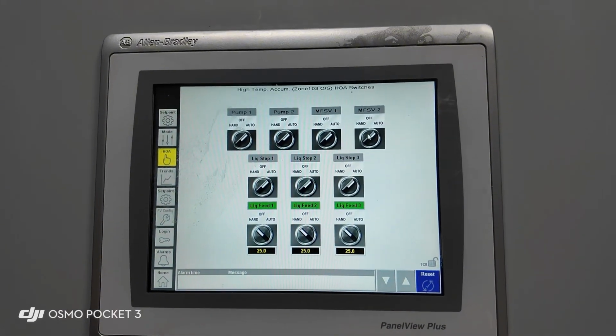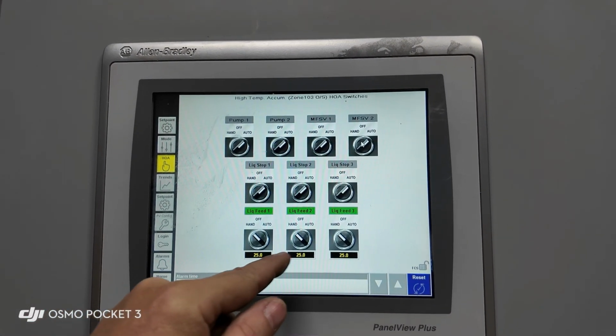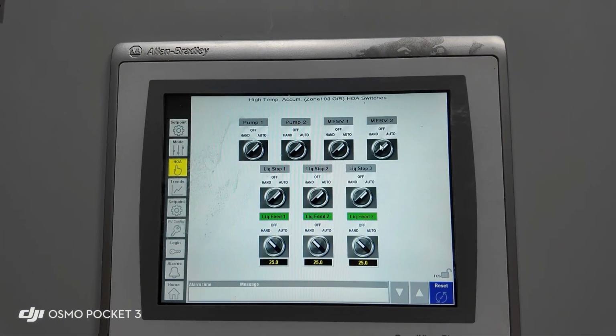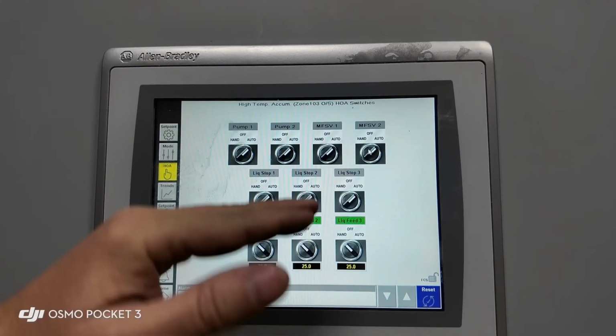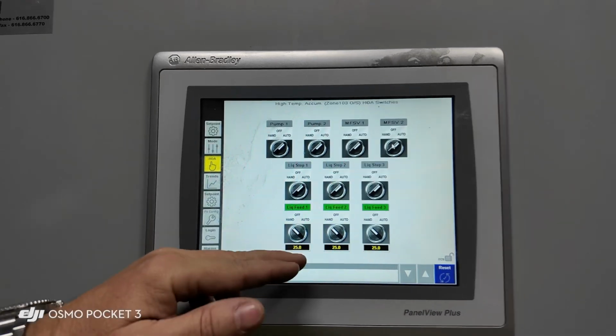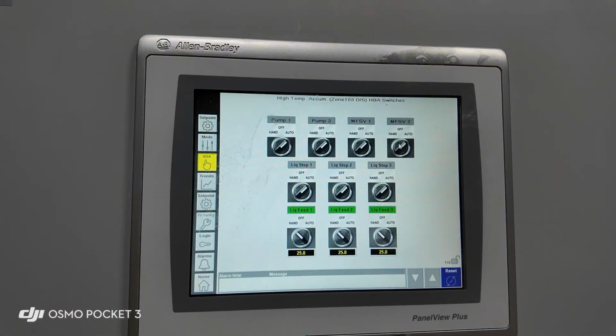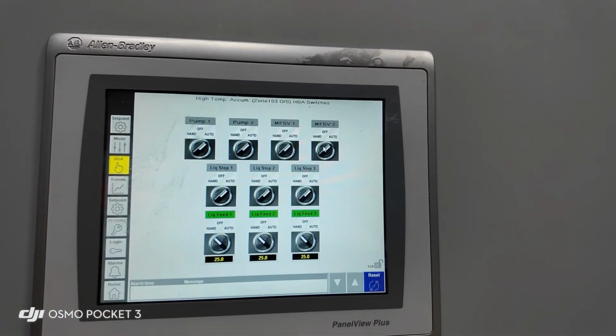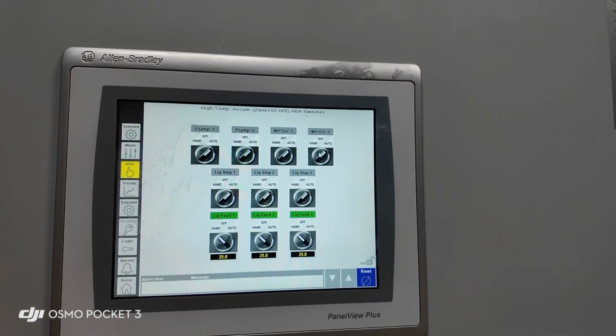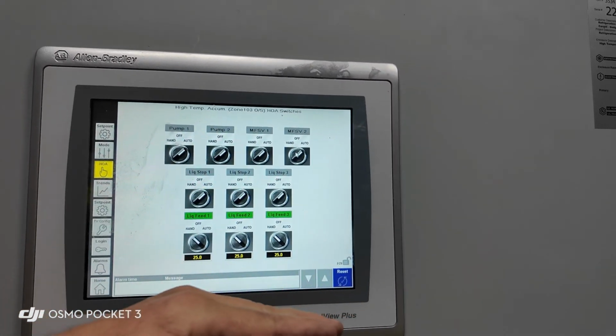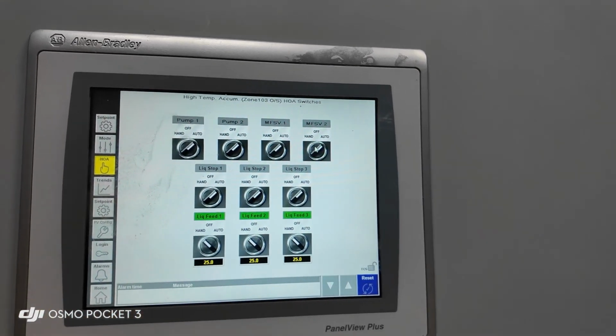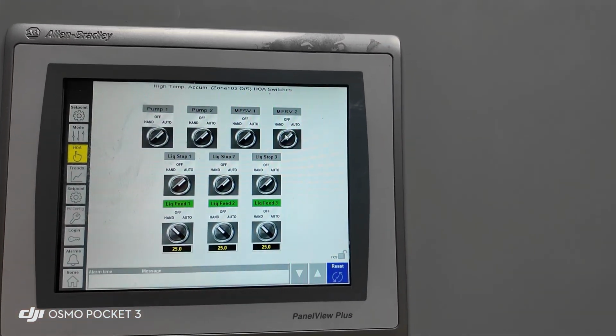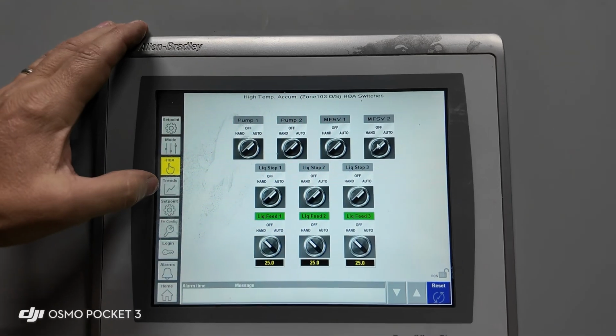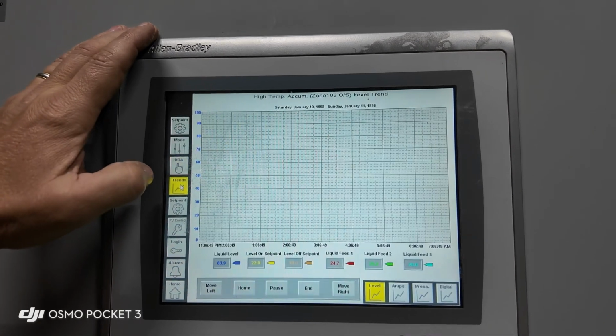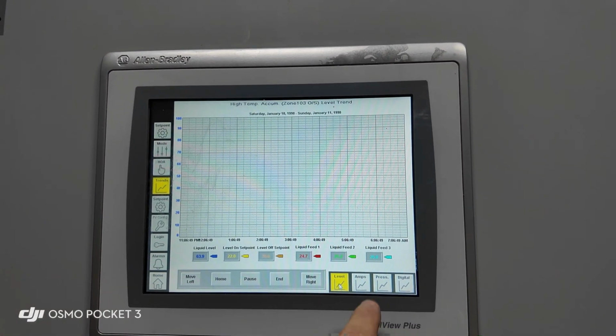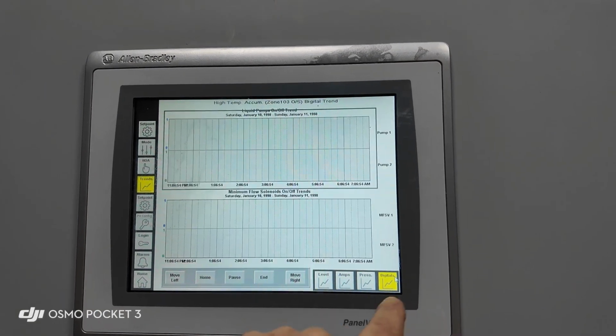When I'm in float control, I must have these in hand, and I set them to use them as metering valves. Okay? They need to be open. If I didn't and my probe were reading 0, these would go automatically out to 100%, and my makeup would be too fast. If the probe had failed high, they would be at zeros, and there would be no makeup. So these must be set to manual when we're in float control to use them as metering valves. We have trend screens, which we can go level trends, amp trends, pressure trends, digital trends.